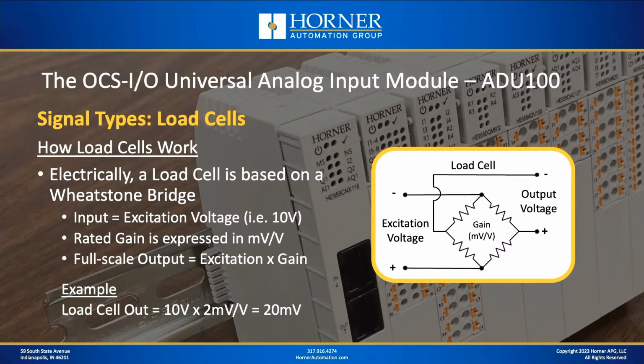So what does that mean? Well, let's say you have a load cell that's measuring 0 to 100 pounds. And if your excitation and gain are as I have it on the screen there, then 20 millivolts will represent 100 pounds, 10 millivolts, 50 pounds, 0 millivolts, 0 pounds, that sort of thing. So that's how load cells work. And as you can see, those are some pretty low signal ranges.